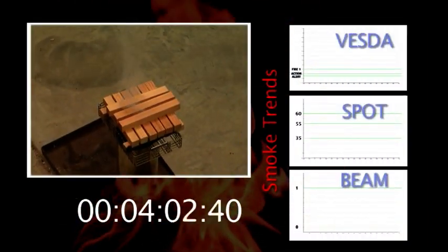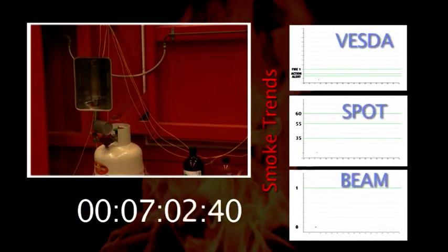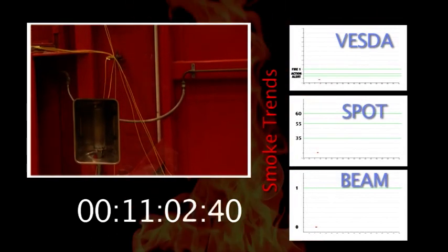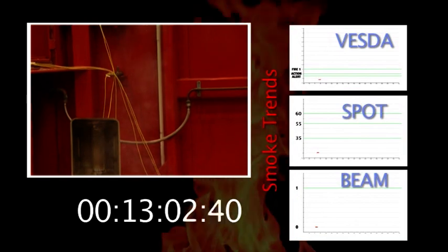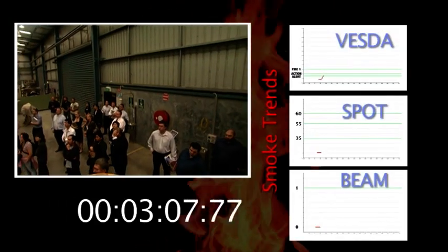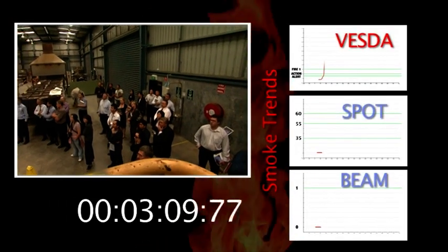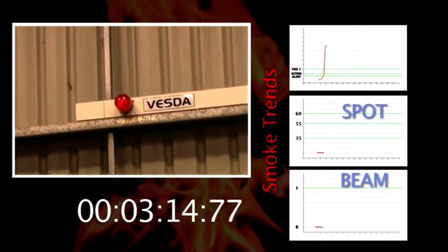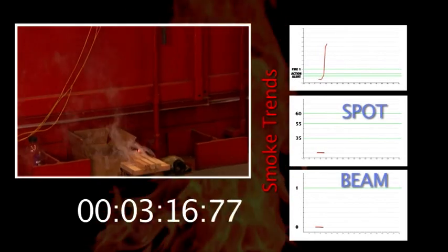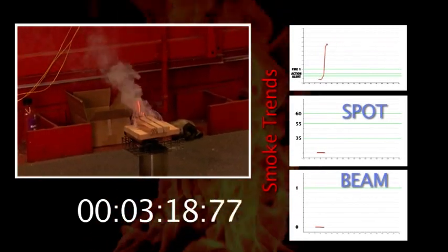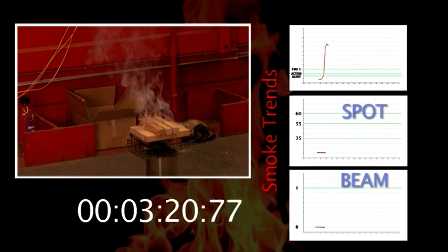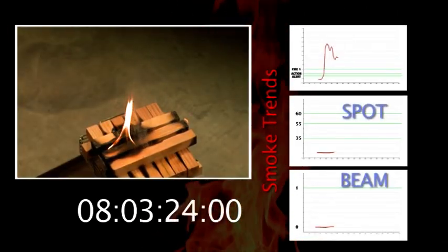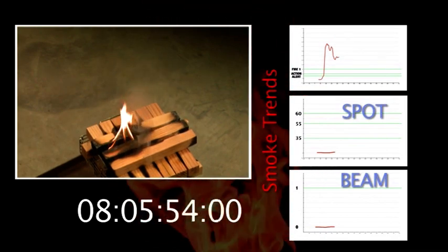The burning of the wood initially undergoes smoldering combustion that generates white smoke followed by flaming combustion with little visible smoke present. At three minutes, the VESDA detector has gone into alert and three minutes twelve seconds into fire alarm one. Meanwhile, as you can see, the fire is still very small and manageable. Eight minutes into the fire and still neither the point or beam detector have picked up the smoke. A clear win to the VESDA system.